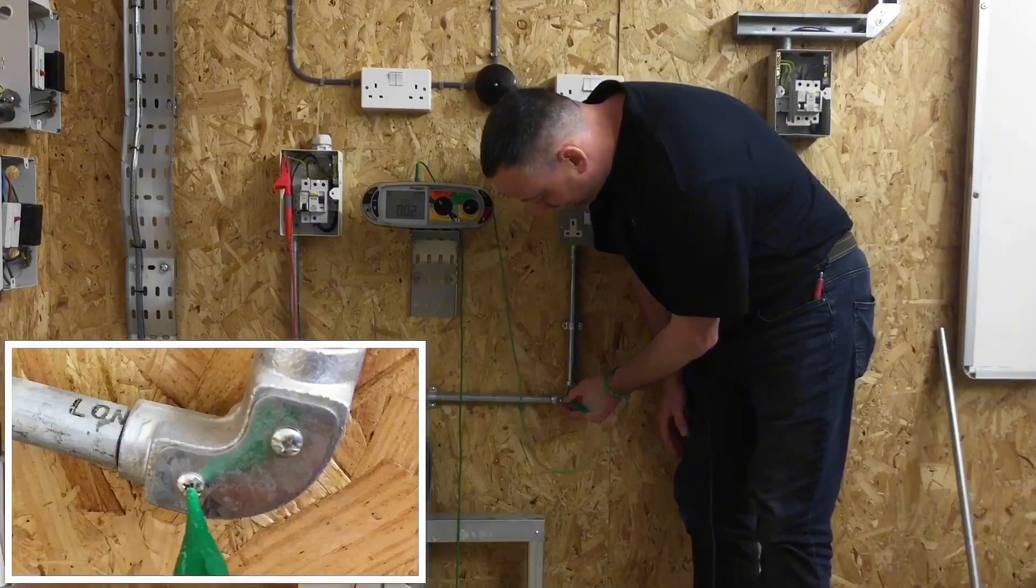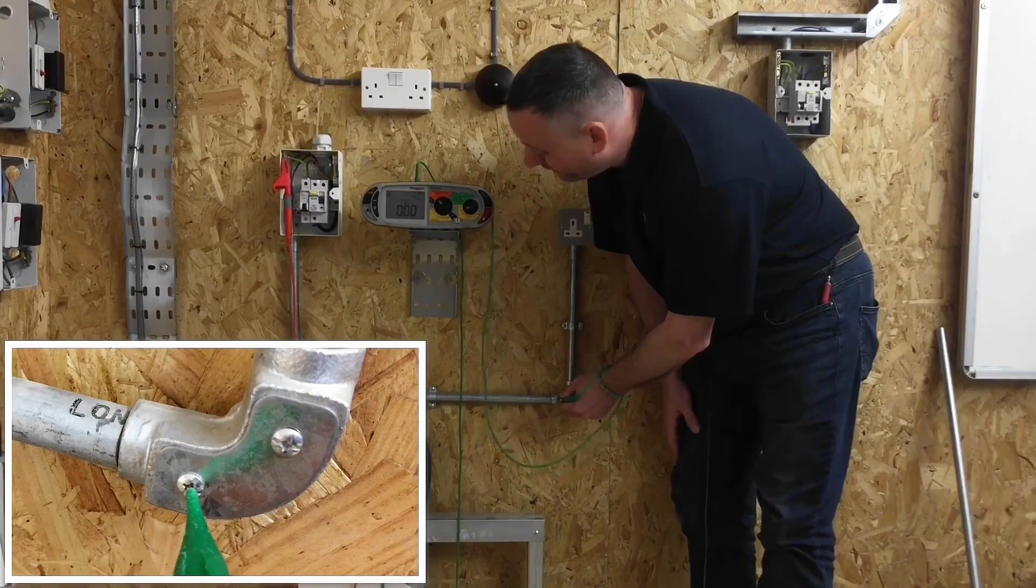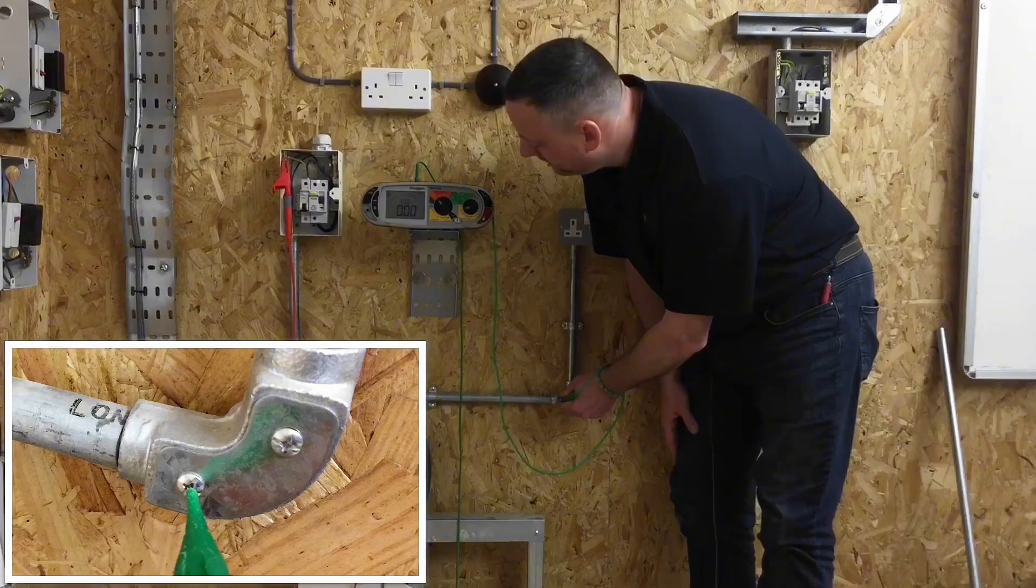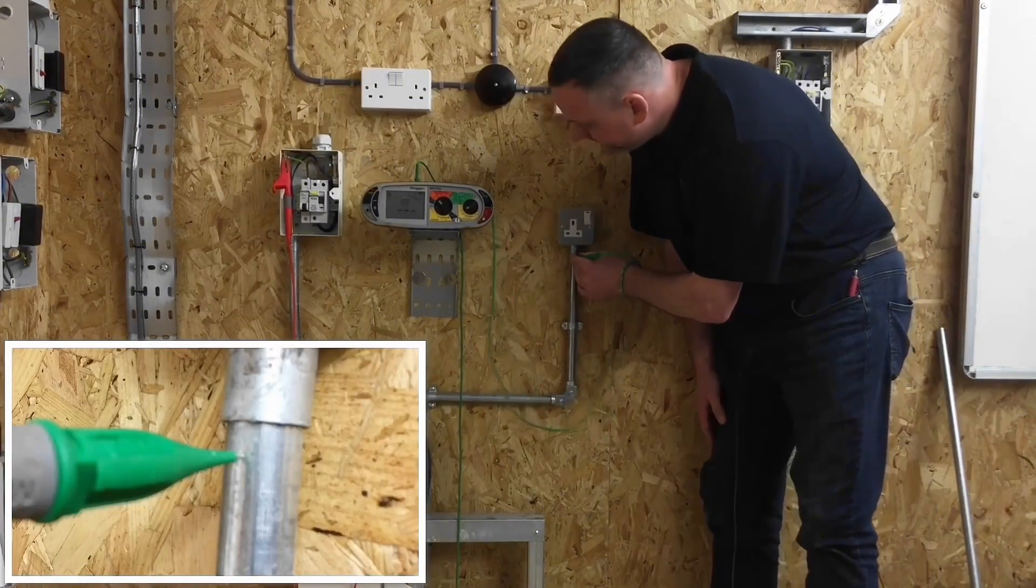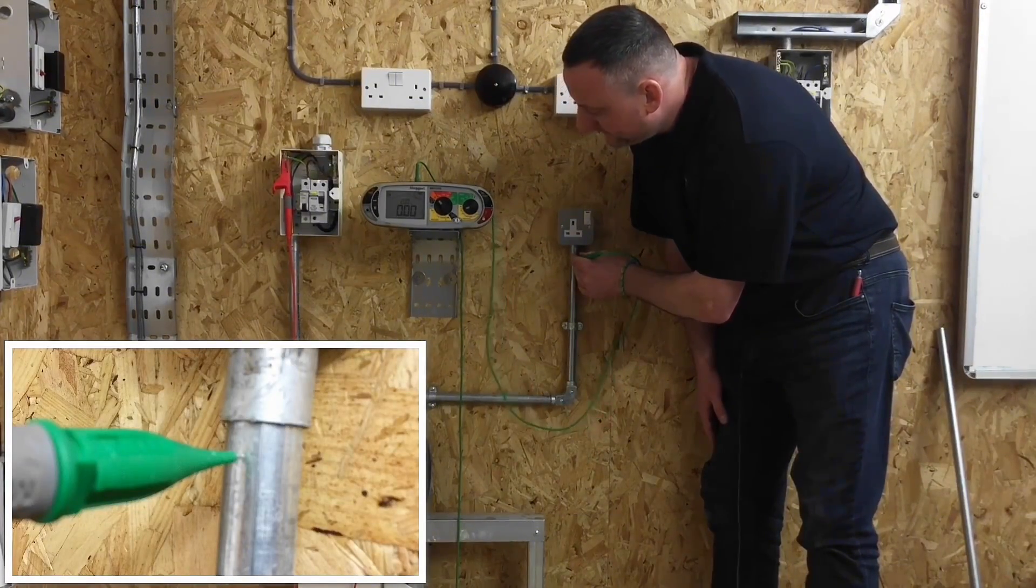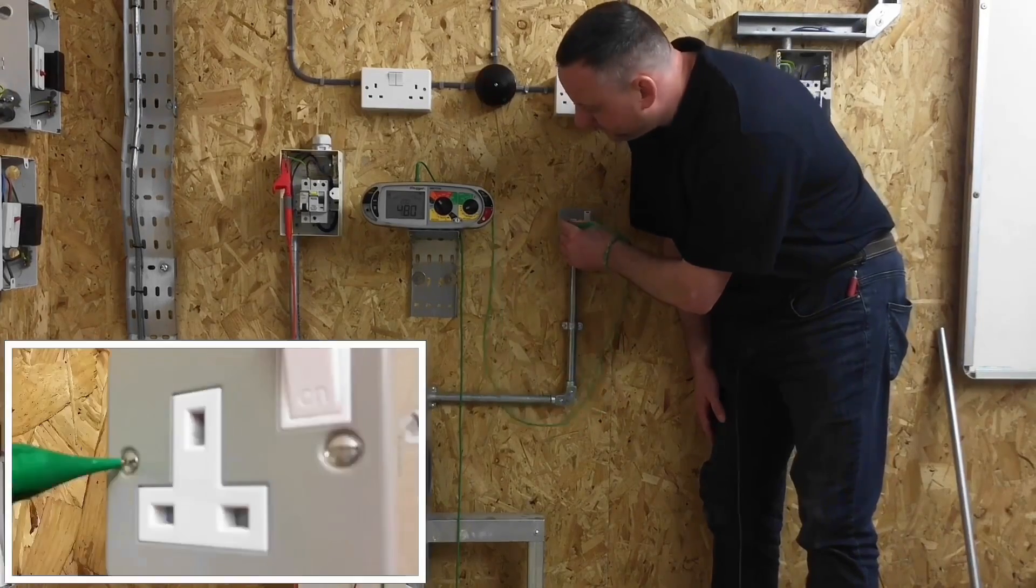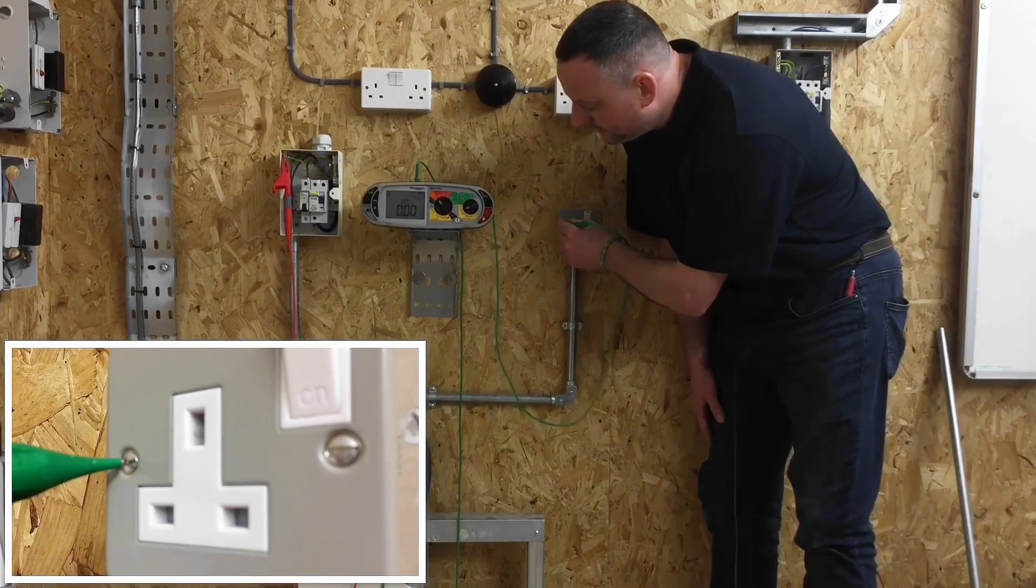So connect onto the conduit itself. I've got a reading of zero, but we explained that earlier. Yep, that's connected to earth. Conduit. Got a reading of zero. And the metal clad socket outlet itself. I've got a reading of zero.